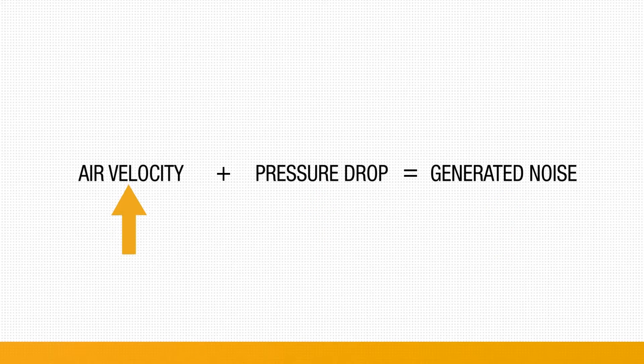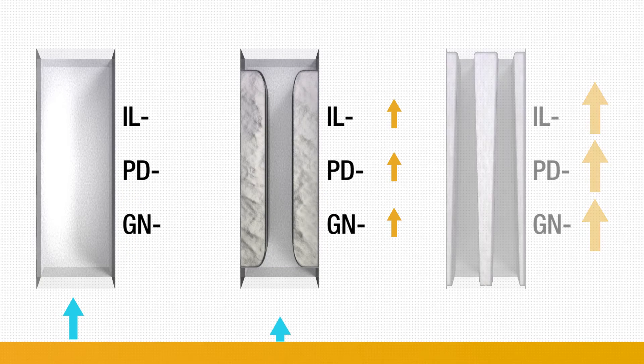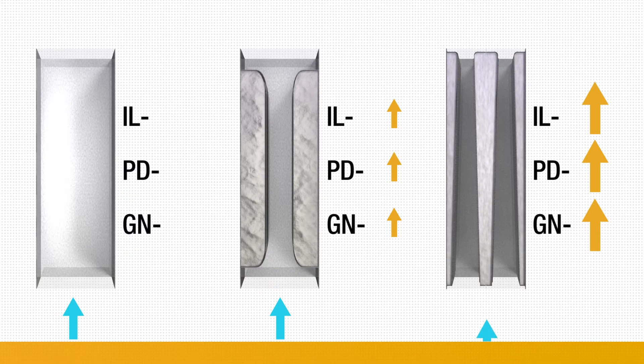A similar pattern is seen with air velocity. When air velocity through a silencer increases, the pressure drop and generated noise also increase. These patterns are seen when the air passage is being impeded by silencer baffles and additional airflow turbulence. While these relationships can be influenced using different baffle geometries and free open areas, the fundamental relationships still apply.